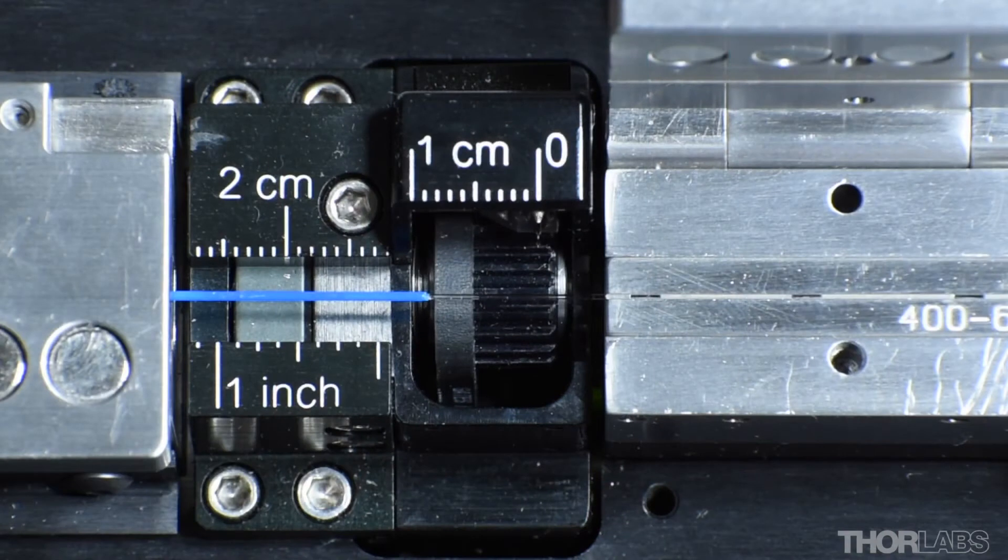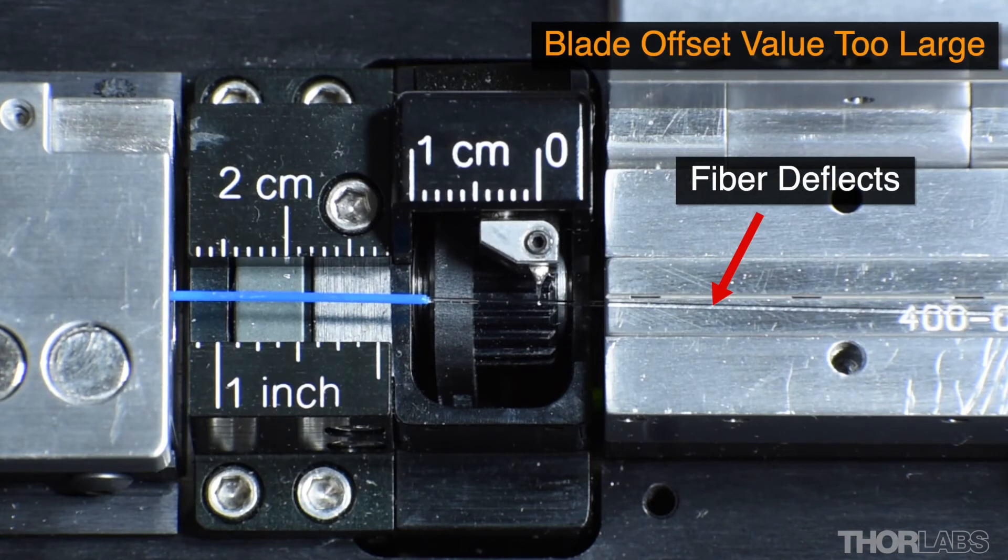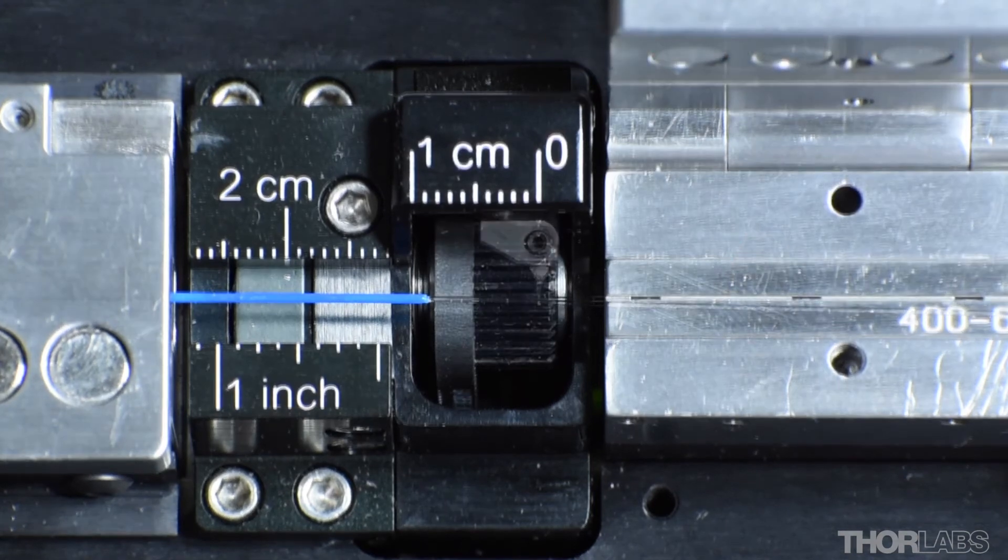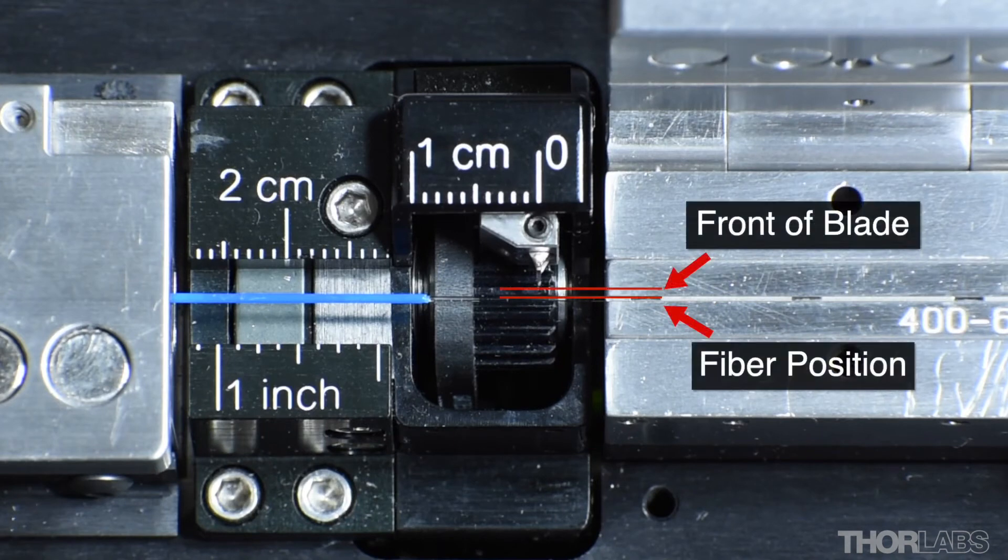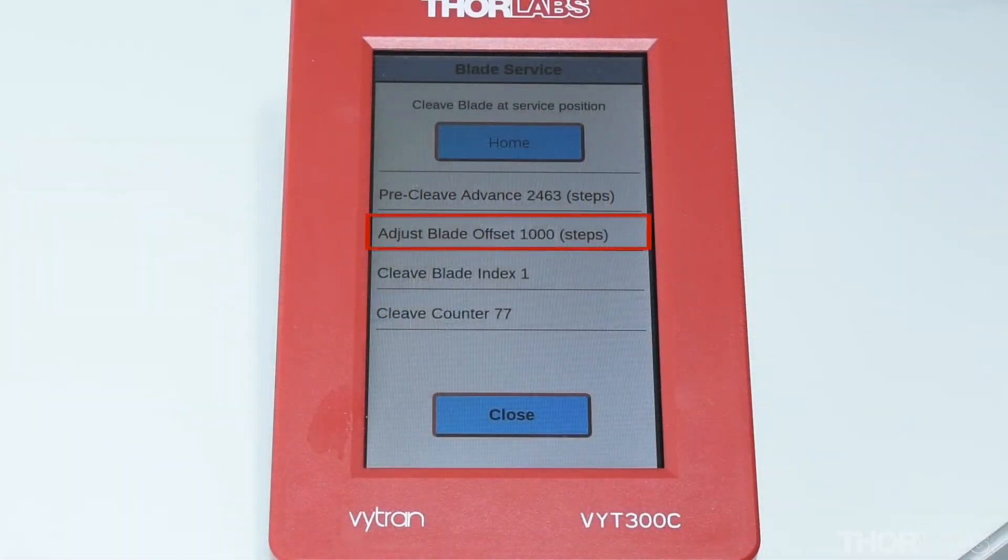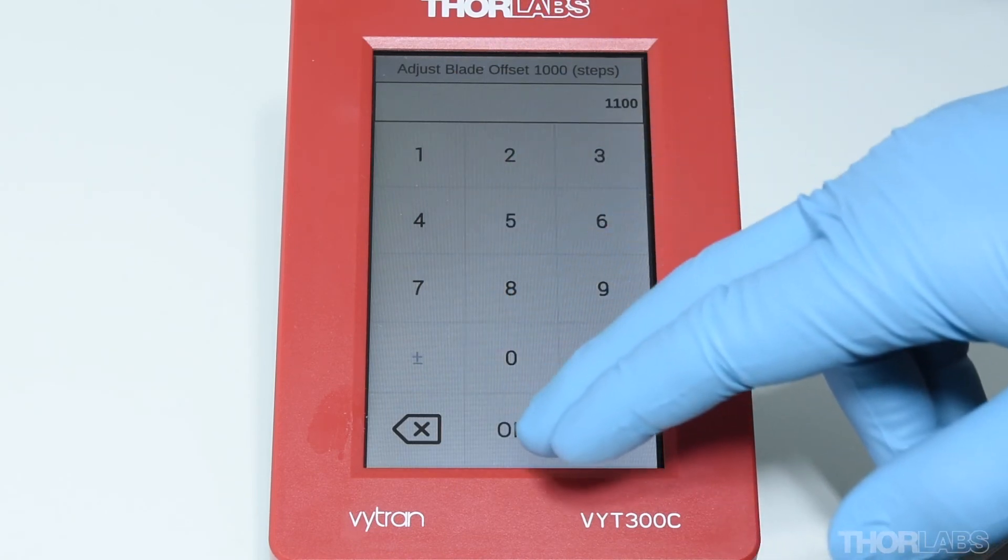If the blade moves so that it touches or deflects the fiber, the blade offset is too large. If the blade moves forwards but its end position is still a long way from the fiber, the blade offset is too small. Adjust the blade offset as required. Changes of only a few tens of steps will be needed if the blade is only slightly misaligned. Larger changes are required if there is a gross misalignment.